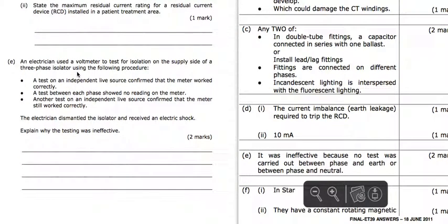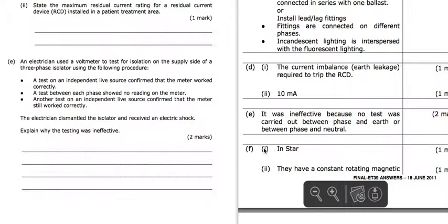An electrician is using a voltmeter to test for isolation on a 3-phase isolator. They've proved their meter, they've tested, but they've only tested between each phase, and then they've proved their meter again, and when they dismantle the isolator they get an electric shock. Well, the testing wasn't effective because they didn't do the test between phase and earth or between phase and neutral. They just tested between the windings. It's not good enough. You need to do all those tests. You need to make sure there's no phase to earth voltage and no phase to neutral.